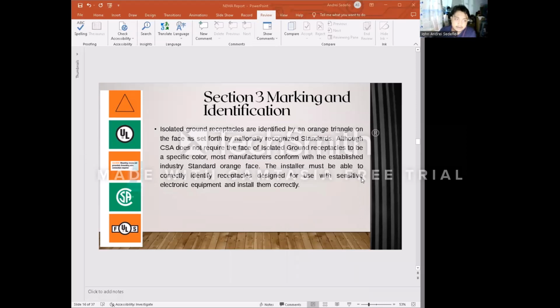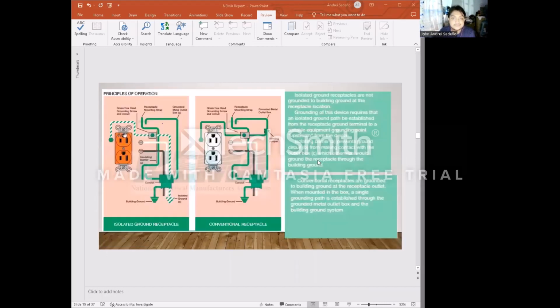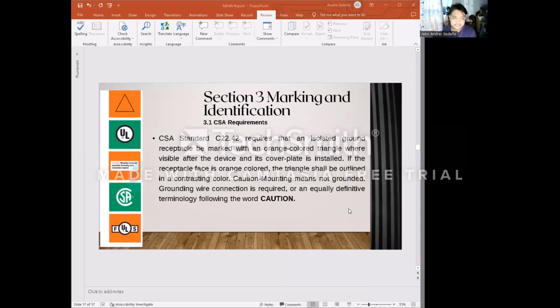So, we can identify an isolated ground receptacle by the color of the orange triangle that you can see on it, which is this. Next is the CSA standard. It requires that an isolated ground receptacle be marked with an orange colored triangle, visible after the device and its cover plate are installed. If the receptacle face is orange colored, the triangle shall be outlined in a contrasting color.